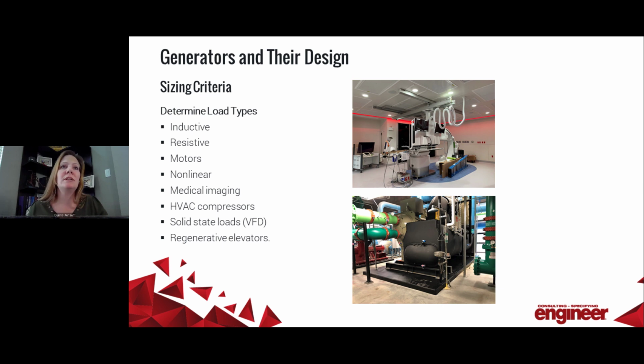Whether they are inductive loads or resistive loads, they have different impacts on the sizing of the system. For instance, inductive loads, which are mainly motors, are going to slow down or stop when you lose power. Bringing them back online as they connect to the generator causes some power transients due to the high inrush currents that exist when they start. This in turn causes a voltage dip.